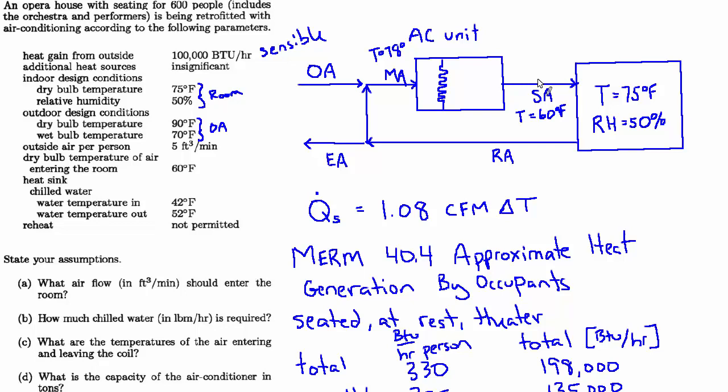And the reason why is because our sensible heat ratio was 0.79. So that means there is a significant amount of latent load, not so significant that it's below the 0.7 mark, and we have to take latent cooling into special consideration. But enough that there is humidity to be removed.